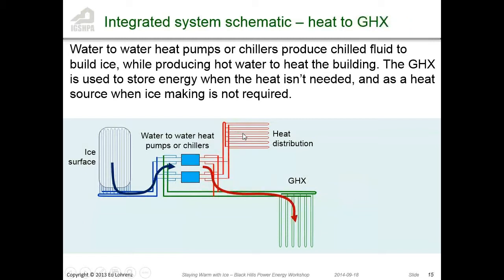Or you can also take heat from the ground loop and put it into the building. The problem with that is solved by the ground heat exchanger: you can store energy when you don't need it, and you can pull energy from it when you aren't producing. Like an ice plant isn't always conveniently running when you want it to be, because the loads are going to be different on the ice rink than they are in the building.